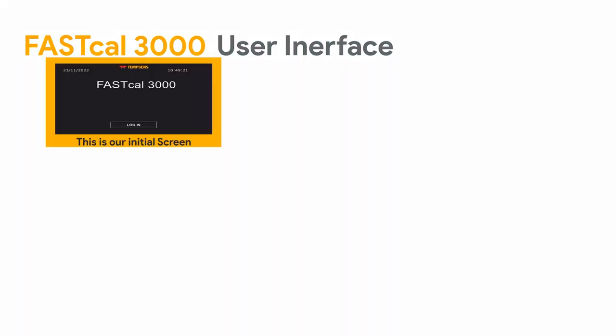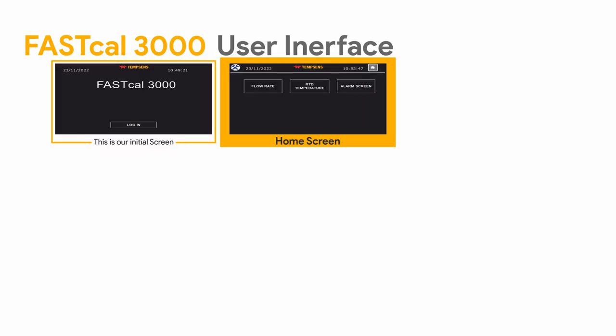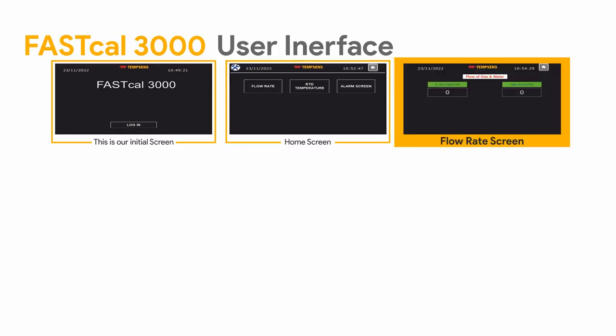Let's walk through the FASTcal 3000's user interface to understand how it works. When the FASTcal 3000 powers on, the initial screen appears, prompting login. The home screen shows flow rate, RTD temperature, and alarm indicators. In the flow rate section, we monitor water and argon gas flows. Argon prevents oxidation in the graphite cavity at high temperatures, while water keeps the copper blocks cool through chiller circulation.